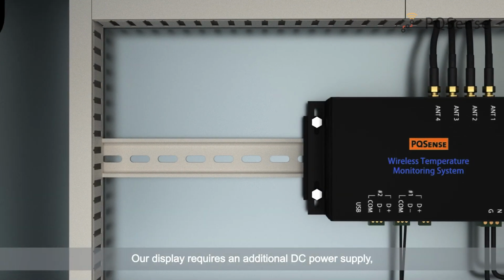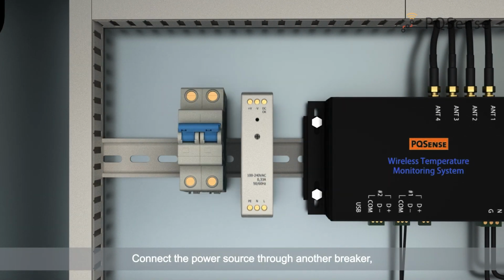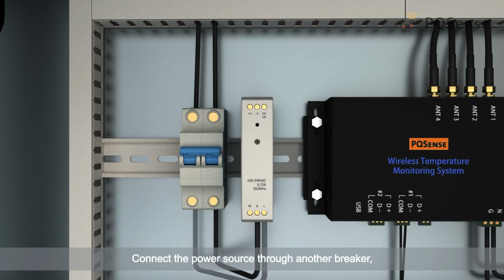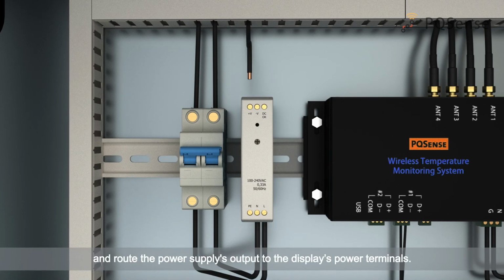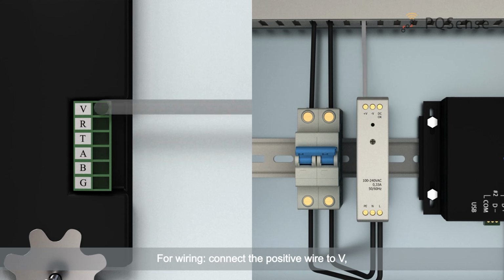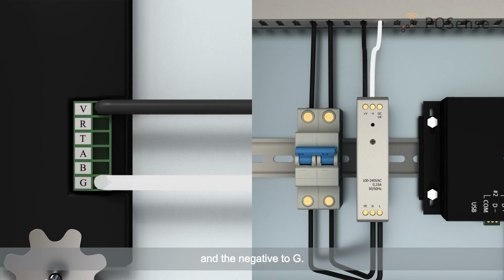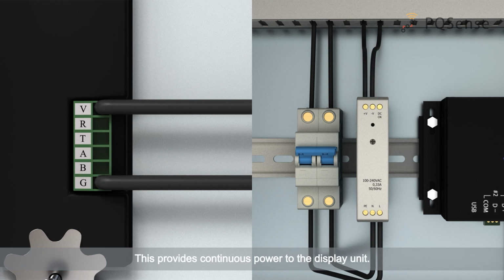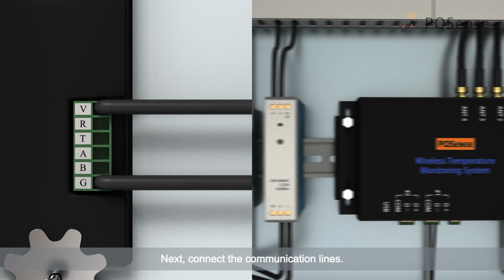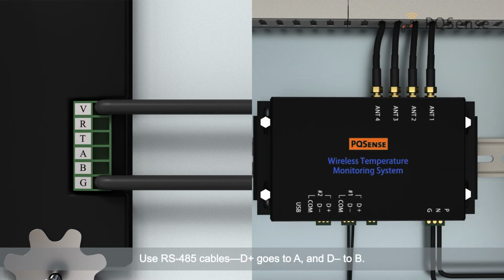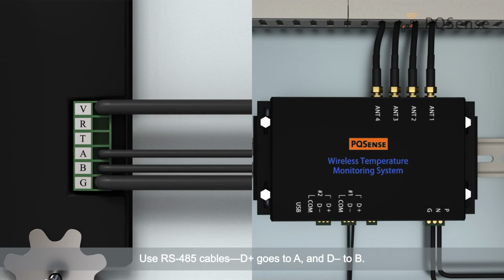Start by powering the display. Our display requires an additional DC power supply. Connect the power source through another breaker and route the power supply's output to the display's power terminals. For wiring, connect the positive wire to V and the negative to G. This provides continuous power to the display unit. Next, connect the communication lines. Use RS485 cables. D+ goes to A and D- to B.